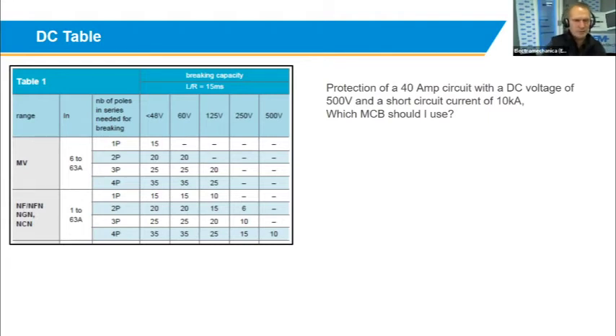So you can then go to the Annex 9, as I said, in the catalog, go to the table, and what you can do is, because I mentioned 500 volts, you can draw a line down from 500 volts to see where the possible fault level can be at 10 kA. Obviously, if it's 6 kA, you can still use the 10 kA product. If it's then 250 volt, you go just a little bit to the left and you draw a line, and you can see that for 250 volt, you can use the same product, just at a different number of poles.